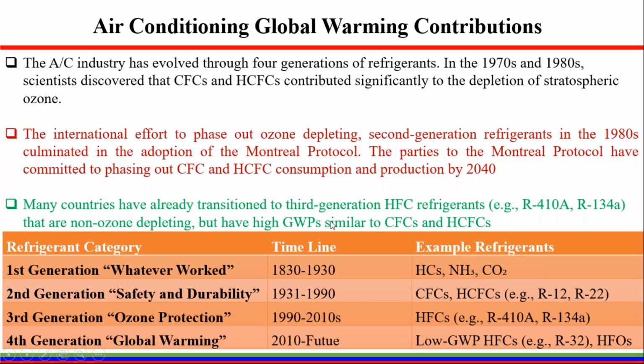And many countries have already transitioned to the third generation hydrofluorocarbon refrigerants that are non-ozone depleting, but their global warming potential is similar to CFCs and HCFCs. But they are non-ozone. They do not react with the ozone because they do not contain chlorine. Any refrigerant that contains chlorine affects the ozone.